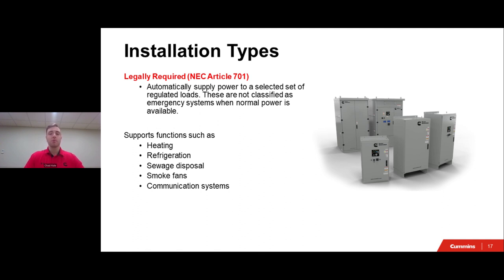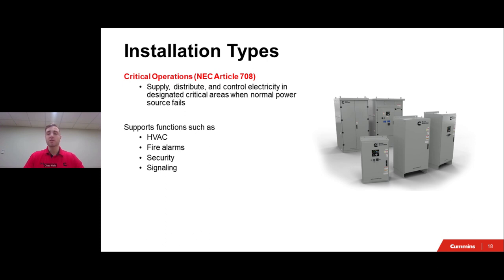Next up on the list, we have critical operations power systems, otherwise known as COPS. Critical operations power systems, or COPS, supply, distribute, and control electricity in designated critical areas when normal power sources fail. They include HVAC, fire alarm, security, communication signaling, and other services and facilities that a government agency has deemed important to the national security, the economy, or public health and safety. All critical operations must meet the requirements of NEC Article 708 of the National Electric Code. Once again, same thing applies with your overcurrent protective devices. They must be selectively coordinated with all supply-side OCPDs. So once again, here's your COPS, supporting functions such as HVAC, fire alarms, security, and signaling.